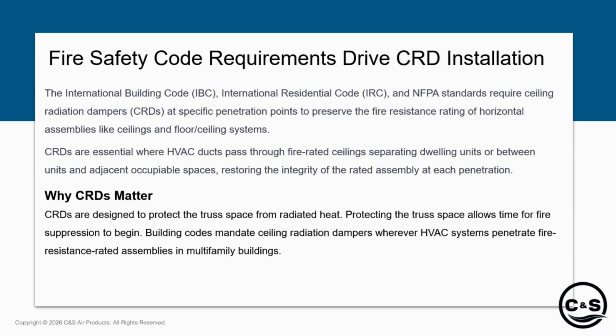A lot of that is driven by code. This goes back years ago, before UL decided to start testing ceiling radiation dampers in the market. The California State Fire Marshal was actually the first entity in the U.S. to test for a radiation damper where you're penetrating through the ceiling. Just a little bit of history before we get into the actual code requirements, but that's where a lot of this started, back in the 70s and 80s, before ceiling radiation dampers were really a thing. People wanted to go straight through the ceiling deck with their penetrations rather than going through an elevator shaft or some sort of drop ceiling. There are a number of different ways to go about it that cost a lot of extra money, and it's not nearly as simple when it comes to installation.